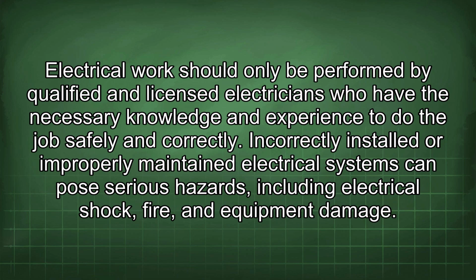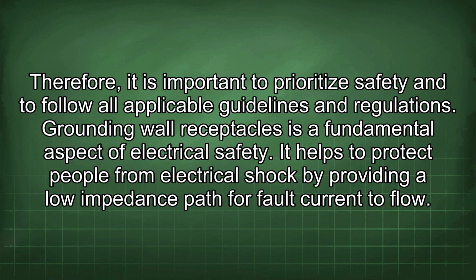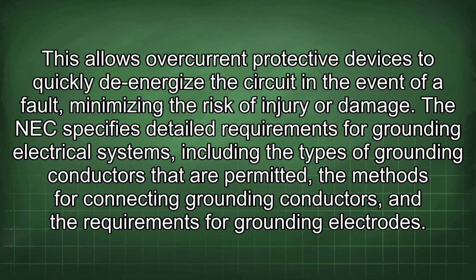Incorrectly installed or improperly maintained electrical systems can pose serious hazards, including electrical shock, fire, and equipment damage. Therefore, it is important to prioritize safety and to follow all applicable guidelines and regulations. Grounding wall receptacles is a fundamental aspect of electrical safety. It helps to protect people from electrical shock by providing a low-impedance path for fault current to flow. This allows overcurrent protective devices to quickly de-energize the circuit in the event of a fault, minimizing the risk of injury or damage.